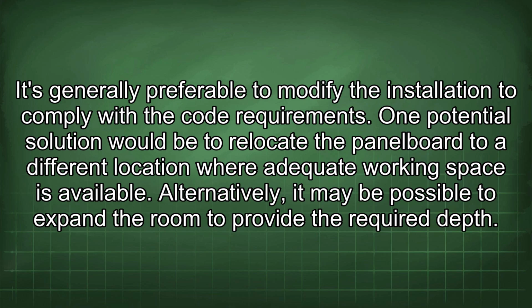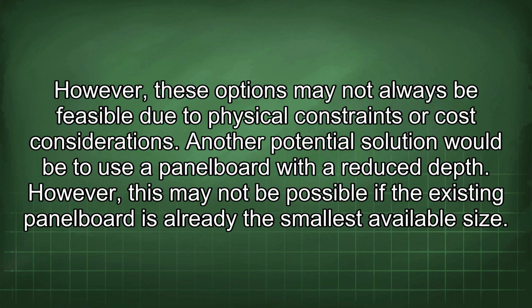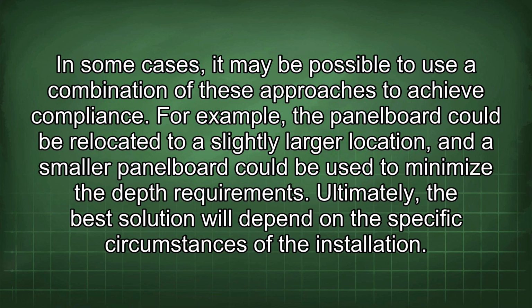One potential solution would be to relocate the panelboard to a different location where adequate working space is available. Alternatively, it may be possible to expand the room to provide the required depth. However, these options may not always be feasible due to physical constraints or cost considerations. Another potential solution would be to use a panelboard with a reduced depth. However, this may not be possible if the existing panelboard is already the smallest available size. In some cases, it may be possible to use a combination of these approaches to achieve compliance. For example, the panelboard could be relocated to a slightly larger location, and a smaller panelboard could be used to minimize the depth requirements.